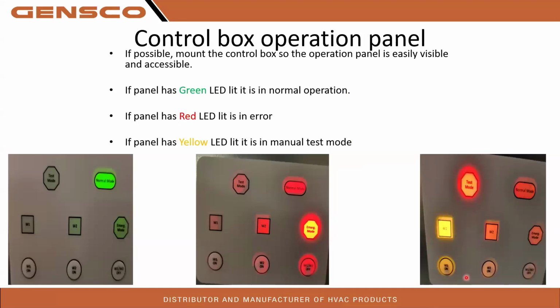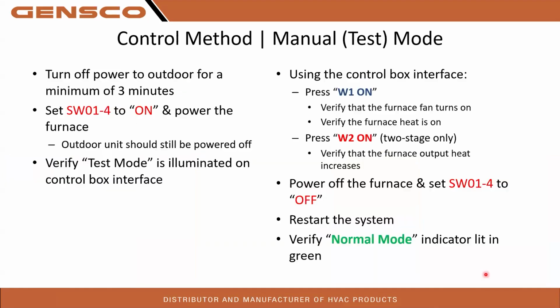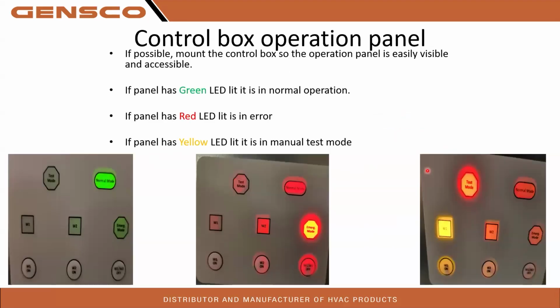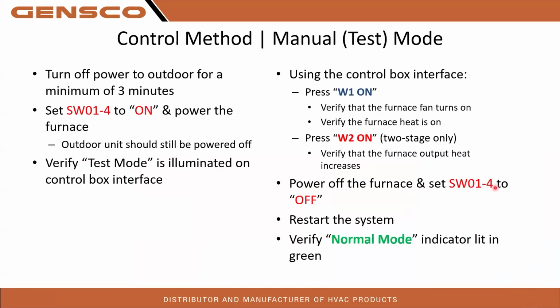Okay. From there, you have the W1, W2 buttons here. So if you want to test your first stage gas furnace, press W1, and verify the fan kicks on and the furnace kicks on. If you have a second stage, then if you press W2, it'll kick on that second stage heat. And then to turn them back off, hit right here, W1, W2 off. That'll turn it back off. And then from there, you can power the furnace back off, change your SW01 switch to the off position, and then restart the system. You're back in normal mode.